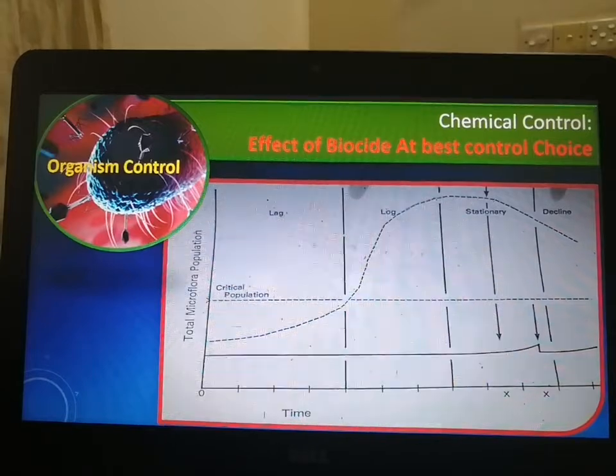And that's why, for oxidizing biocide in a big system, we always prefer to dose continuously, or at least dose intermittently, maybe morning and evening, or for a small system every day in the evening or early morning. So what happens if we dose every day? Every 24 hours the number slightly goes up again. If we dose again after 24 hours with a sufficient amount of the right product, then again it comes down to the same level, and it continues for another 24 hours. So 24 hours is the intermittent dose. And if we dose intermittently, or continuously, with any good quality effective oxidizing biocide, the system microorganisms should remain in this range.